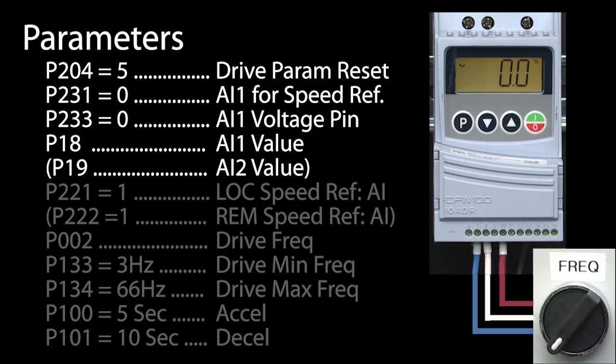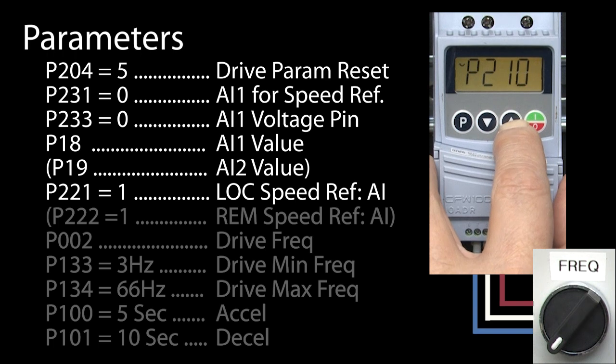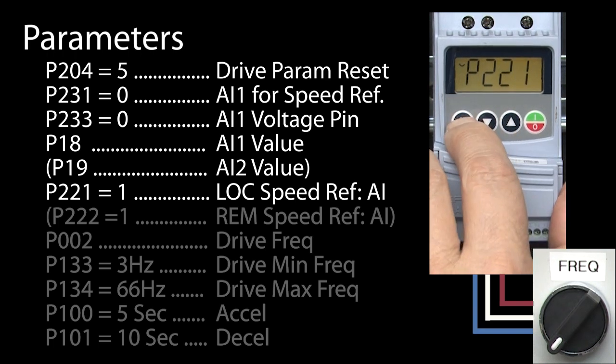So the only thing left to do is tell the drive to use the potentiometer on analog input 1 and not the keypad to control the frequency of the drive, which will control the speed of the motor. To do that, we go to parameter 221 because we are using the drive in local mode.